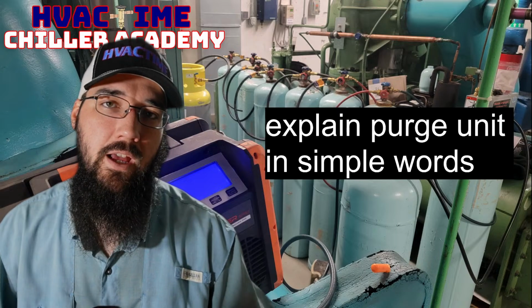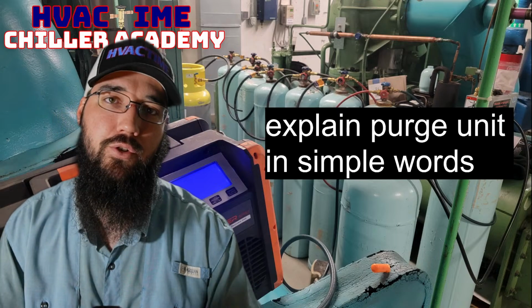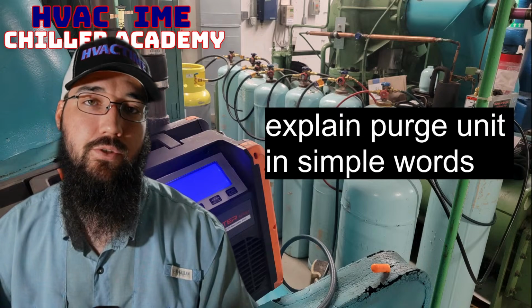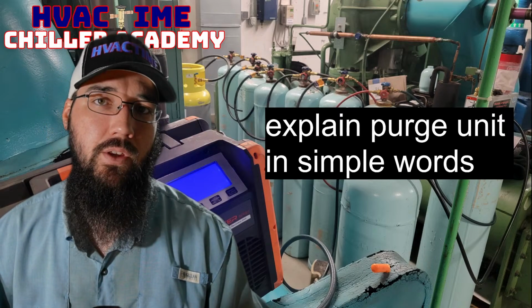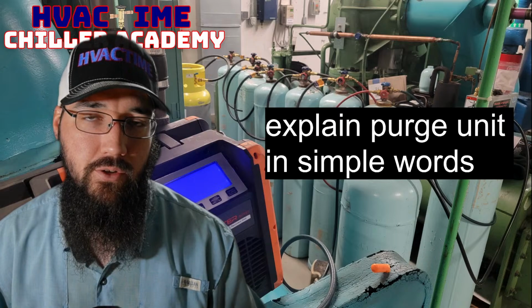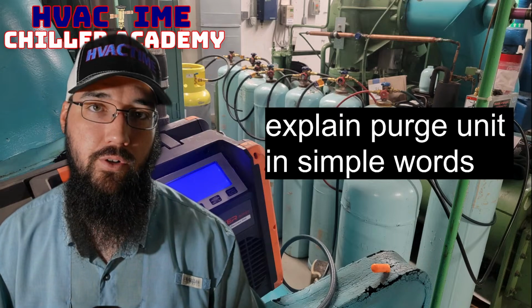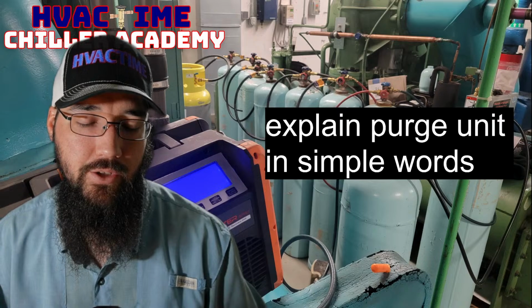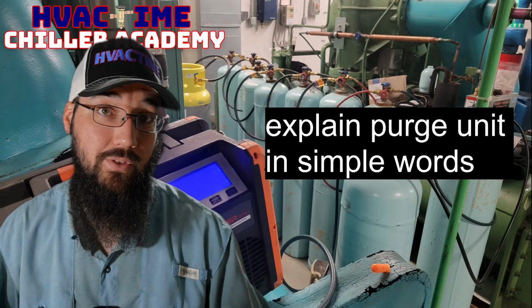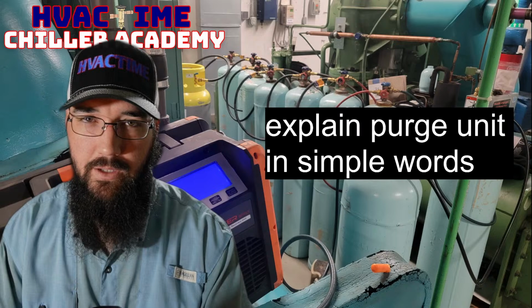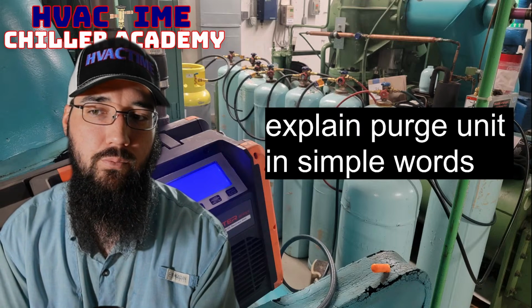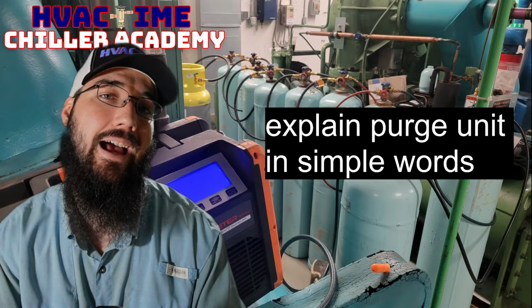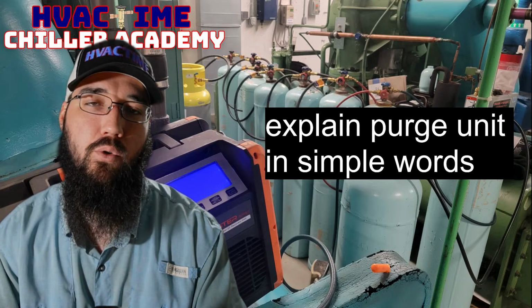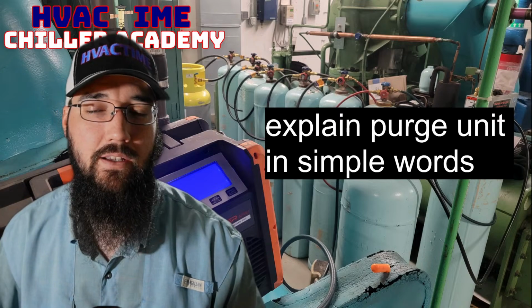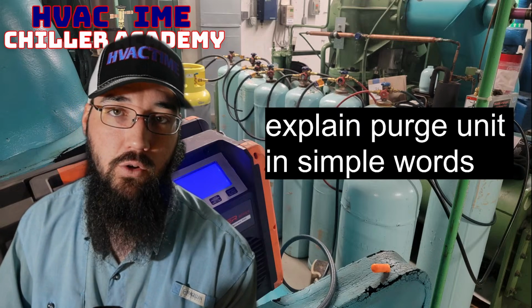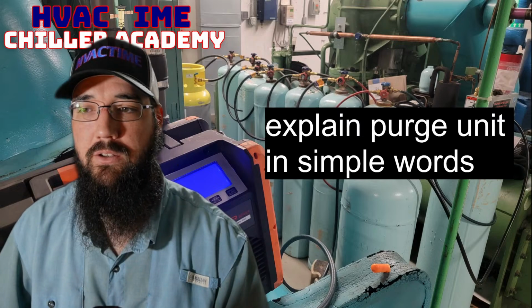And so sometimes having a portable purge, you can come in as a part of your maintenance procedure or your annual startups and let that purge run on that chiller for a little while before you try to do a startup and then immediately go into surging issues due to the non-condensables that happened over the off season. Again, just some of the things to think about and consider, and how having a portable purge is really effective, and if you're doing a lot of low pressure work, a needed aspect of your toolkit.